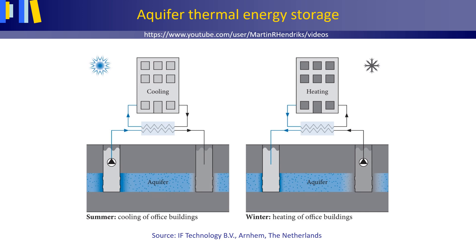At Utrecht University, we have an aquifer thermal energy storage project in use. The saturated hydraulic conductivity K, as used in Darcy's law, strongly depends on the groundwater's temperature. Therefore, calculations of the volume flux Q and the effective velocity of groundwater in aquifers used for thermal energy storage should always take this into account.